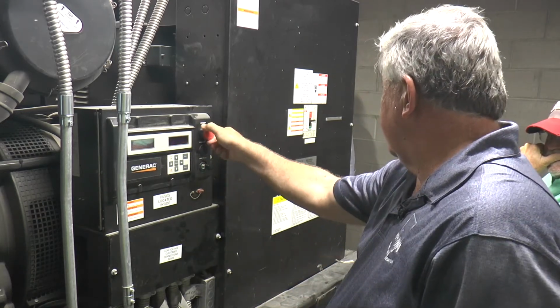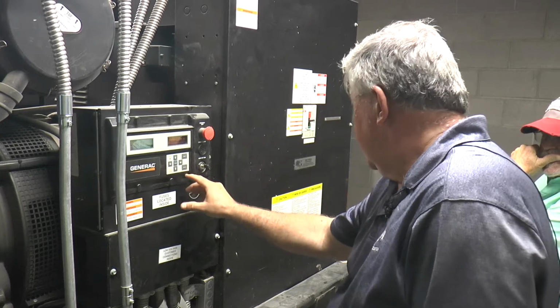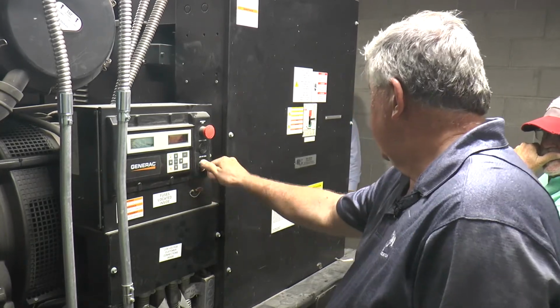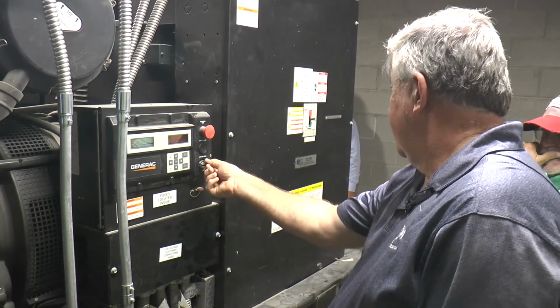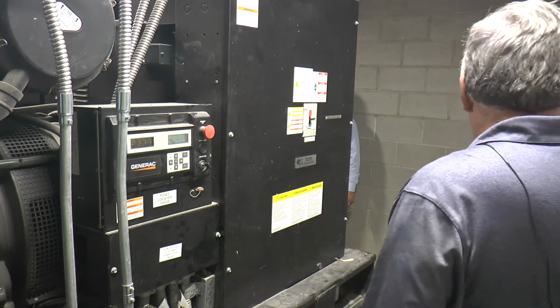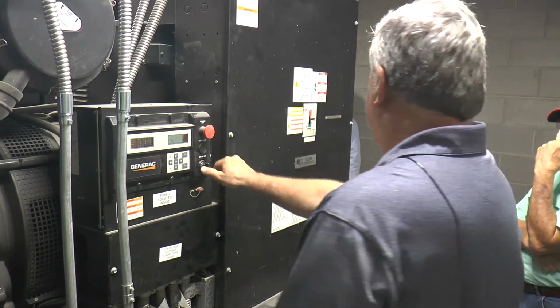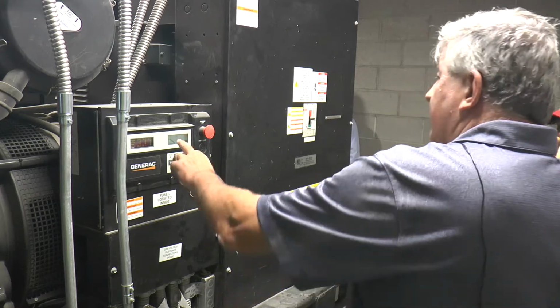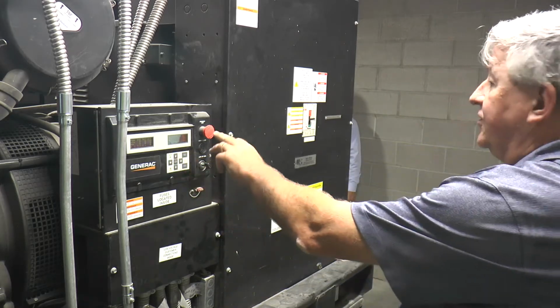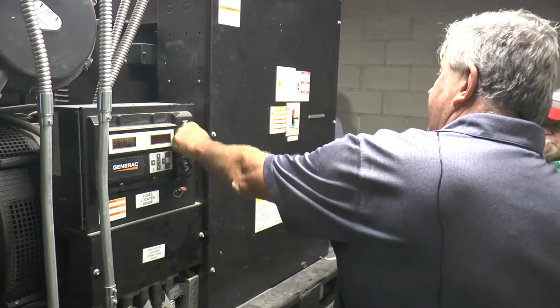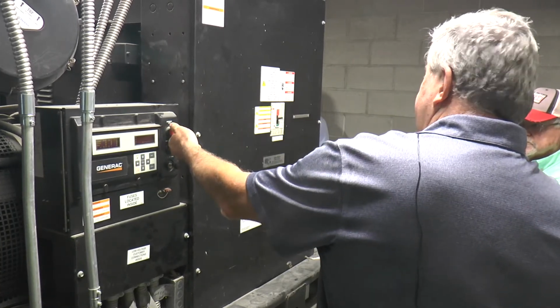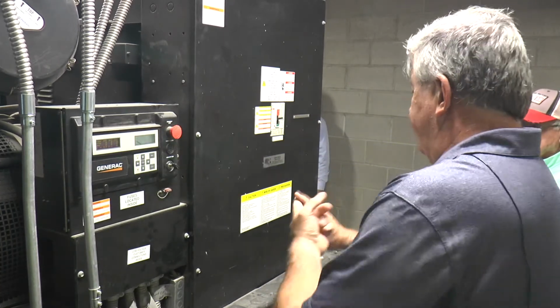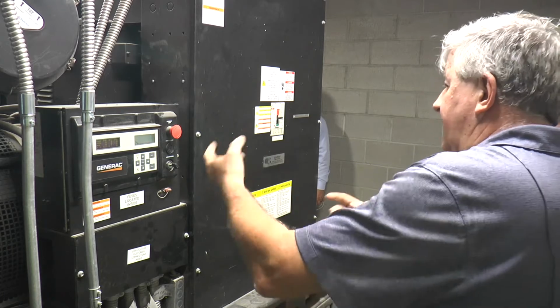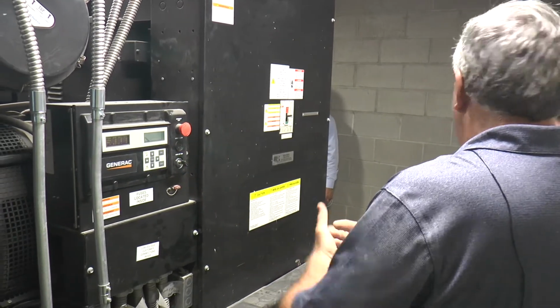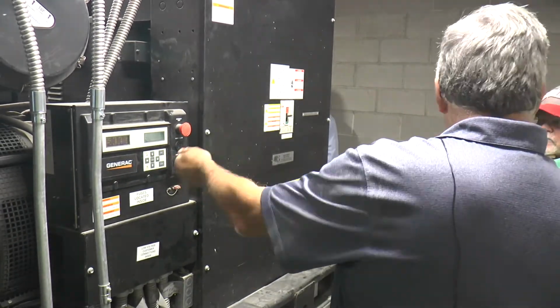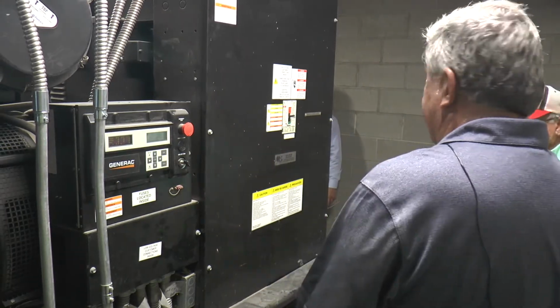So to clear the fault, bring it back out, go to acknowledge, put the key to off, bring it back on. Now the system's back in auto. But you have to put the key back to off to clear the fault, but you also have to acknowledge the fault that it's cleared. And clearing it, these keys are just a quarter turn. So if you have a high water temp alarm, it shuts the engine down, you have to fix the fault, clear it, off, reset, you're set and ready to go again.